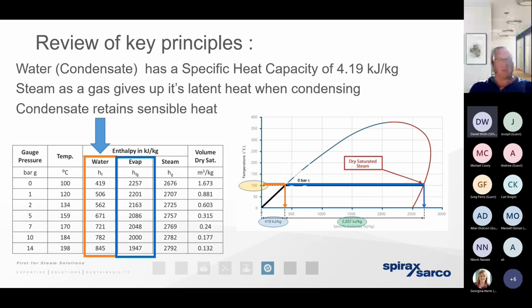Now, if we quickly move across to the opposite side of the screen, that's what shows the temperature enthalpy curve. In other words, it plots the journey that water takes as it changes state from a liquid in the boiler to produce steam as a gas. So the orange line demonstrates the energy that we need to add, in the case of 0 bar gauge, 100 degrees, for the water to hit boiling point. Anything more than that is going to result in the water starting to evaporate to produce steam. But it's only when we've added all of the energy identified in the blue box that we're going to get 100% dry saturated steam.